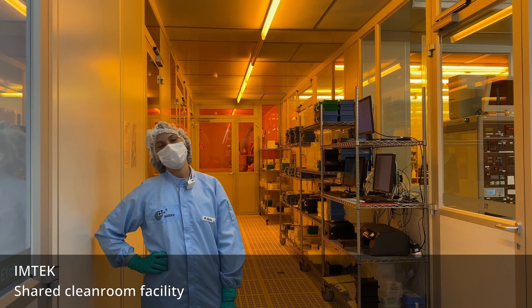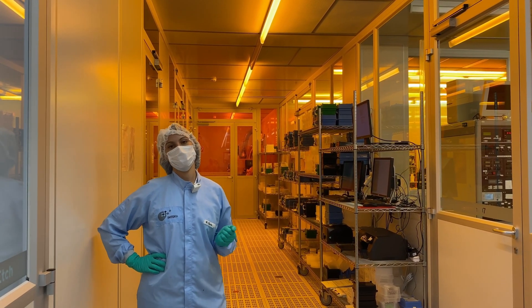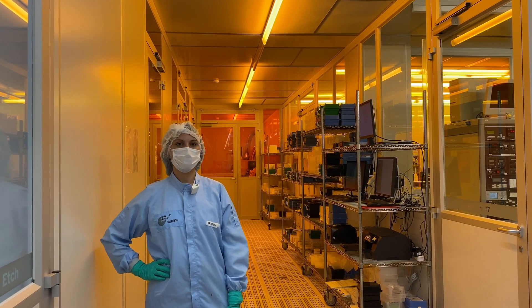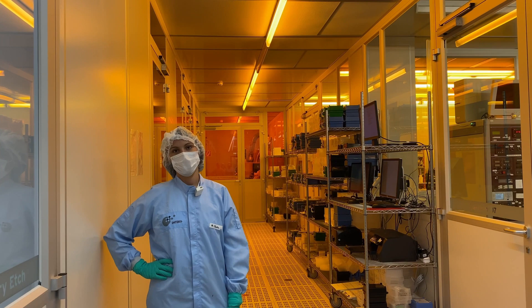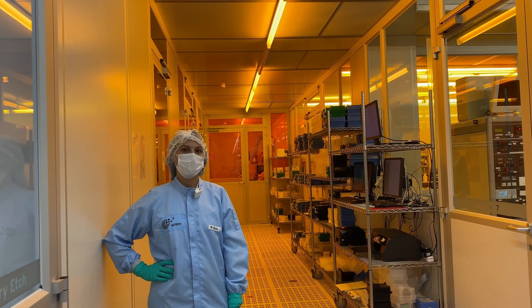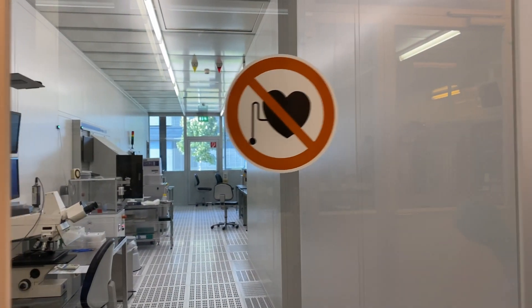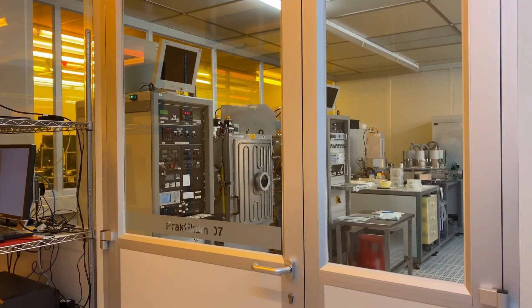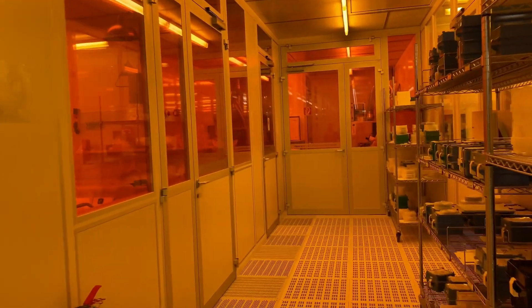Here we are in our clean room. It's a shared clean room of the whole IMTEK. It has an area of 600 square meters and the clean room class can be varied between 4 and 7 through an individually controllable filter system. We use this clean room for three steps of our wafer fabrication: an O2 plasma step to clean our metallization, a physical vapor deposition process to deposit our metallization on our wafers, and a photolithography step where we spin coat our photoresist on our wafer.